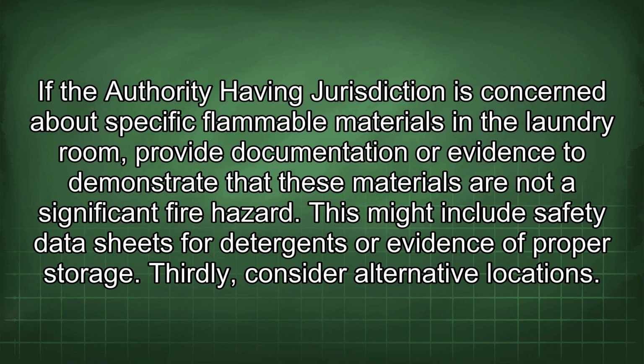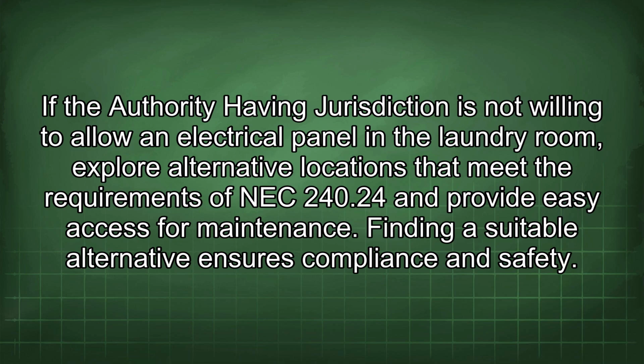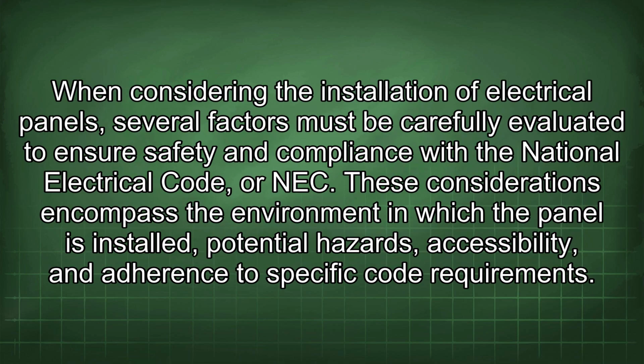Thirdly, consider alternative locations. If the authority having jurisdiction is not willing to allow an electrical panel in the laundry room, explore alternative locations that meet the requirements of NEC 240.24 and provide easy access for maintenance. Finding a suitable alternative ensures compliance and safety. When considering the installation of electrical panels, several factors must be carefully evaluated to ensure safety and compliance with the National Electrical Code, or NEC. These considerations encompass the environment in which the panel is installed, potential hazards, accessibility, and adherence to specific code requirements.